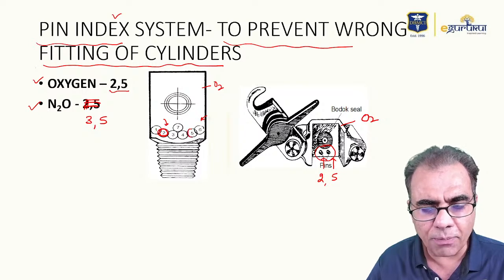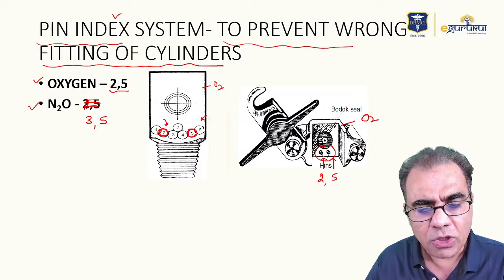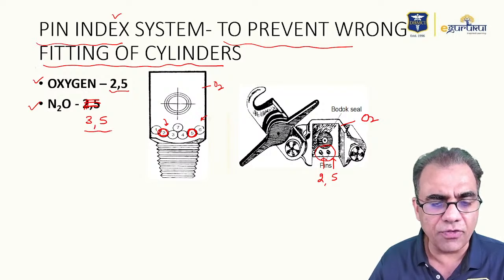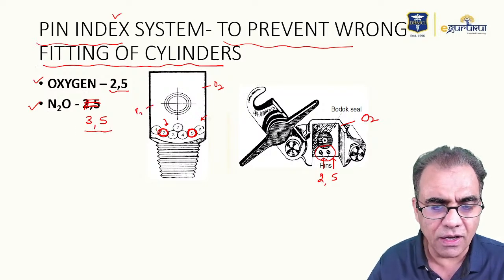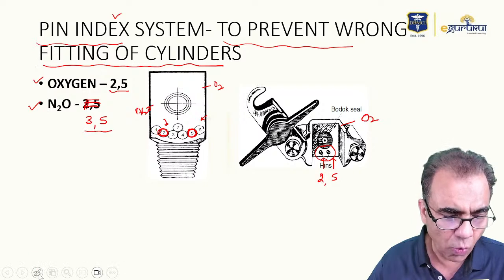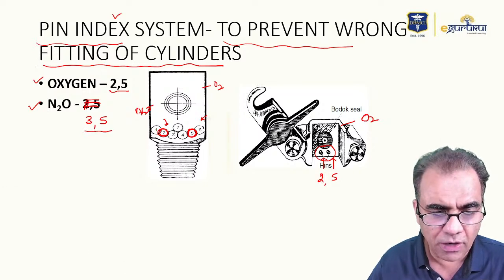So that holes and pins will match with each other. So the pin index for nitrous oxide is 3, 5. It means if it is a nitrous oxide cylinder, the positions of holes will be 3 and 5.